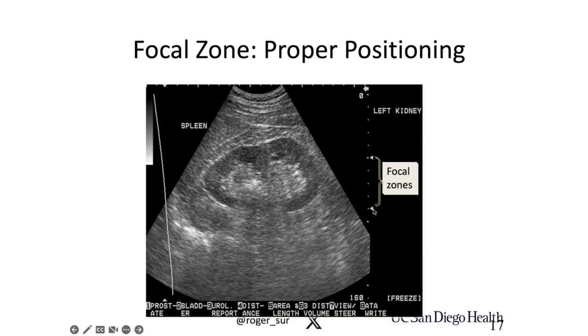Between two focal zones, if there are two on here, is where the region of interest will be best highlighted—the fidelity of the image will be really good between these two lines. Sometimes you may only have one focal zone, say just this triangle here. That would mean anything below this point is the focal zone. So it depends on how many symbols you have. One focal zone means anything below it is the area of interest; two focal zones means it's the area between them. Some newer machines no longer have these focal zones—they automatically focus. I don't know how they do it, but they do.